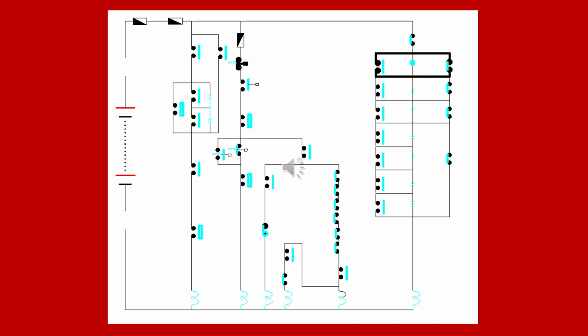We are frequently using these fuses. Why? Because there may be a short circuit in the DC circuit also, so the fuse will melt to protect the loco. Okay, so this is the system. Then we will do fault isolation and check where the fault is.